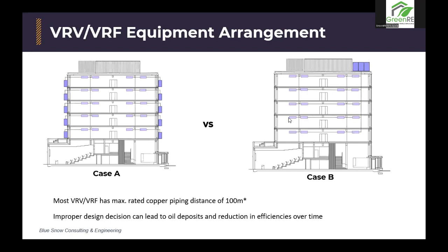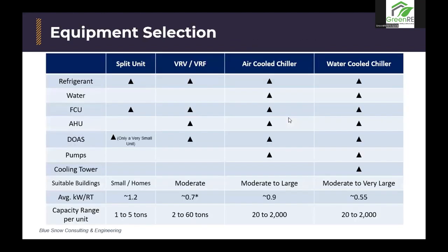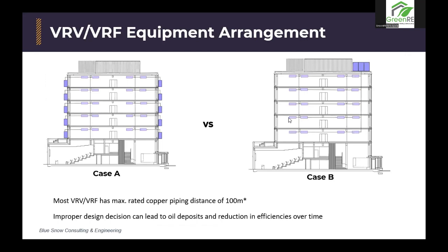Case A also, I say the same contractor does case B and case A. Case A will be able to handle the screw-up much better because your copper pipe length tends to be a little shorter. So even if you end up with a contractor who's not well versed, the design approach gives it a bit of a buffer so that it can handle a bit of the screw-ups that happen in the copper pipe installation. So I just wanted to highlight that in case anybody was wondering why there is a 0.7 with an asterisk there, because an improper installation can lead it to lose its efficiency rather quickly, within 5 years. So that's something to bear in mind when coming to VRV and VRF systems.